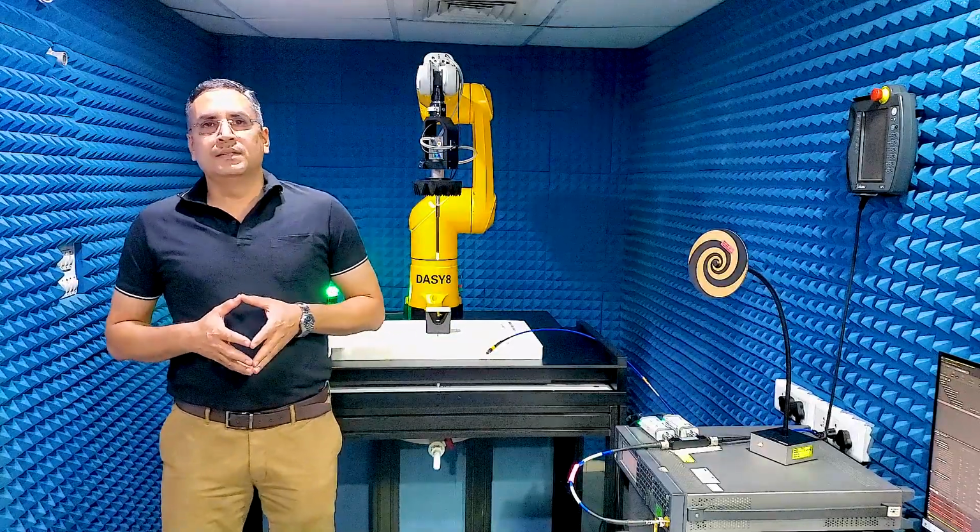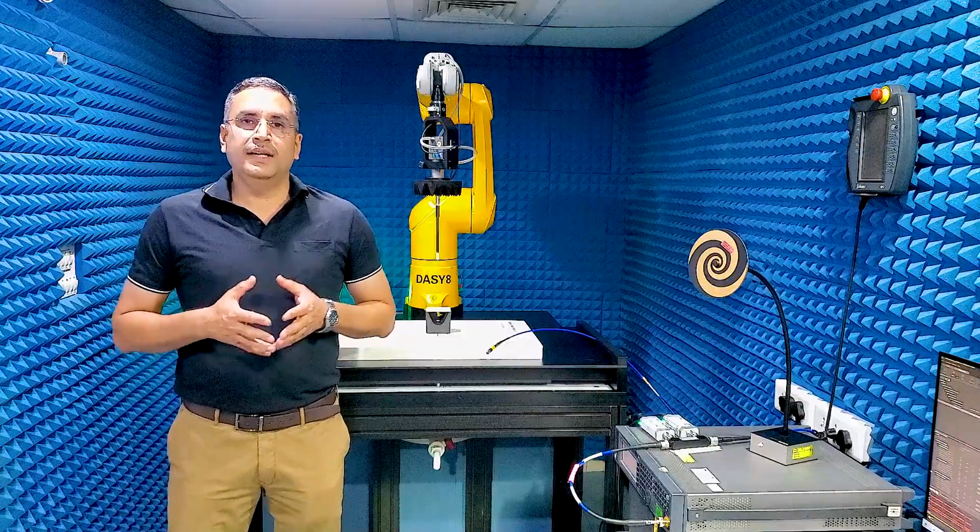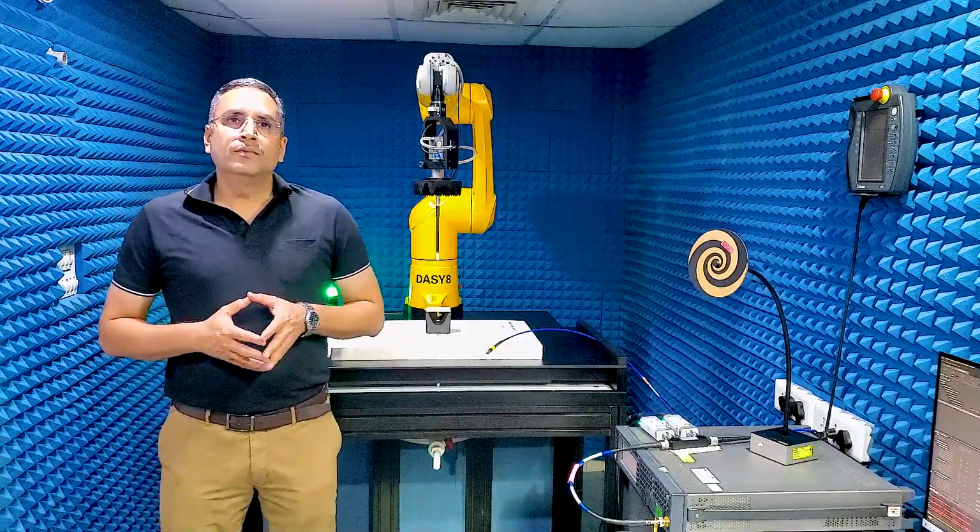SPEAG asked us to test the latest software release of DASY8 Module SAR, which is version 16.2. According to the release notes, version 16.2 adds several new features and improvements. The most important one is the capability to evaluate multi-transmission specific absorption rate in specific phantoms. For example, smartwatches when tested on the wrist phantom, or virtual reality goggles tested with the face down phantom.